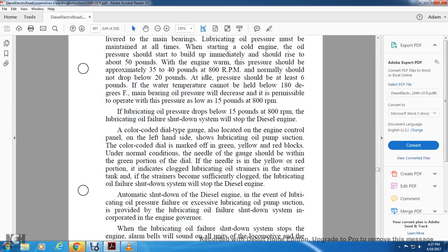A color-coded dial type gauge, also located in the engine control panel on the left side, shows the lubricating oil pump suction. The color-coded dial is marked with green, yellow and red blocks. Under normal conditions the needle of the gauge should be within the green portion. If the needle is in the yellow or red portion, it indicates a clogged lubricating oil strainer. If the strainer tank becomes sufficiently clogged, the lubricating oil failure shutdown system will shut down the diesel engine.